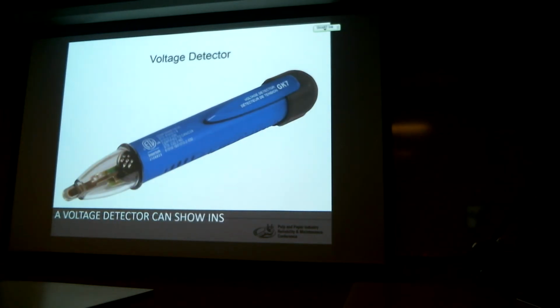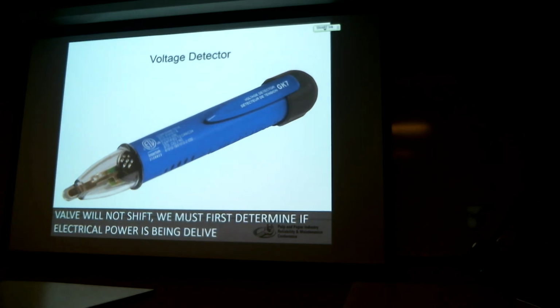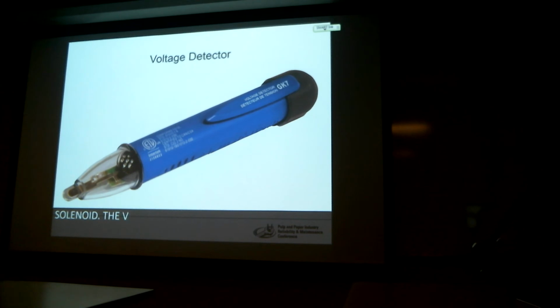A voltage detector can show instantly if a solenoid is being energized. When the directional valve will not shift, we must first determine if electrical power is being delivered to the solenoid. The voltage detector will light up when the voltage is present.